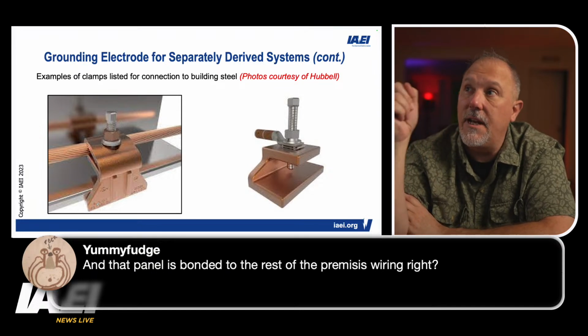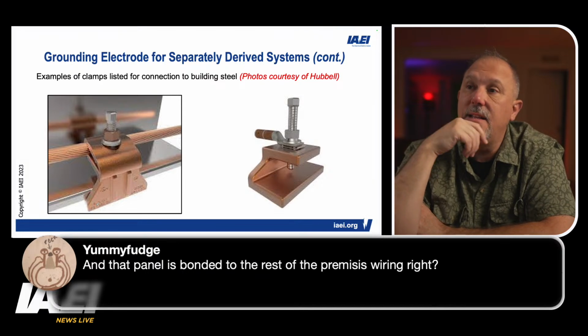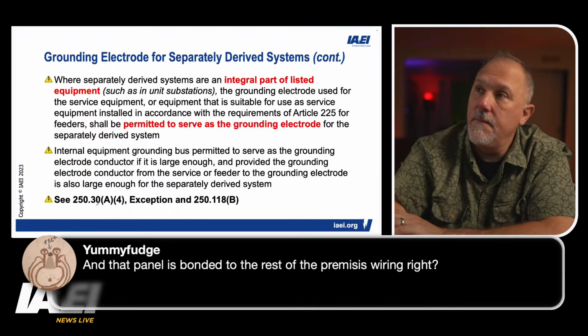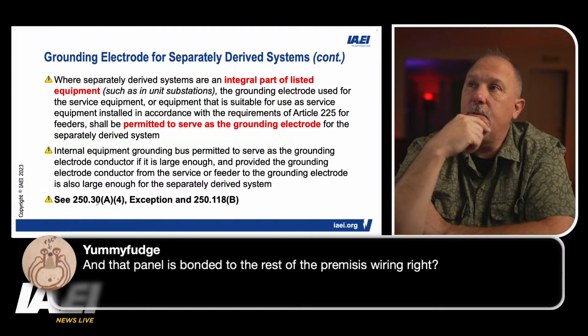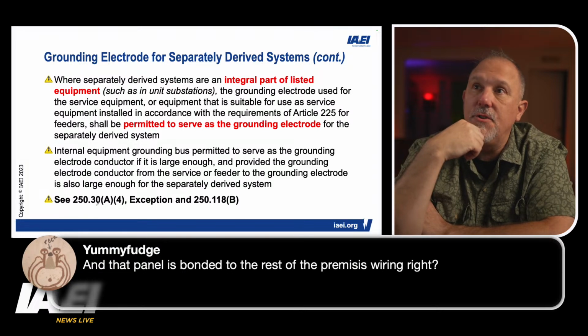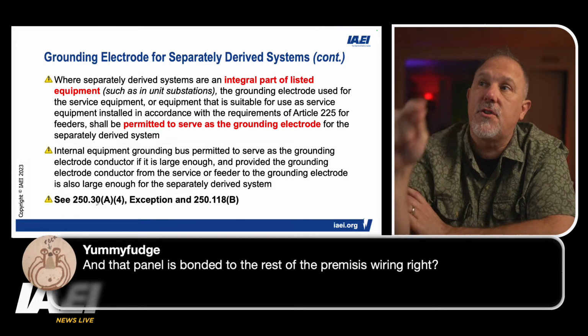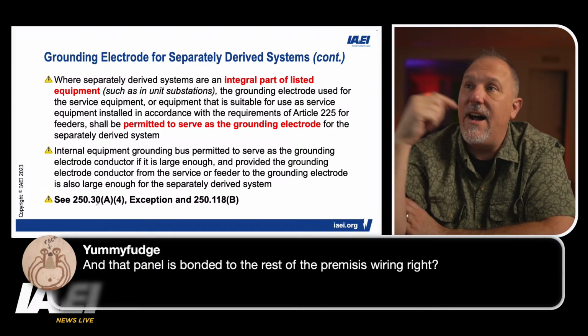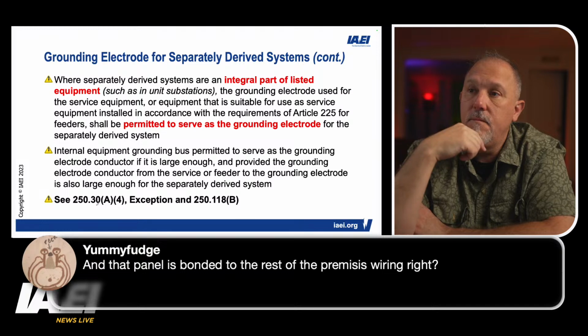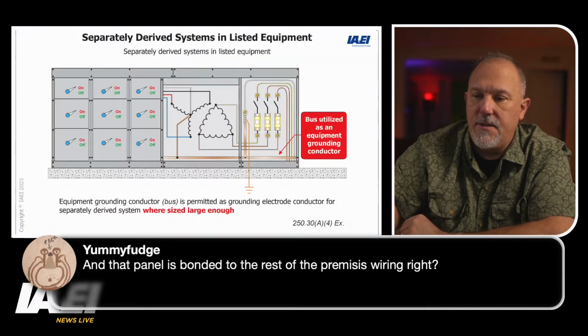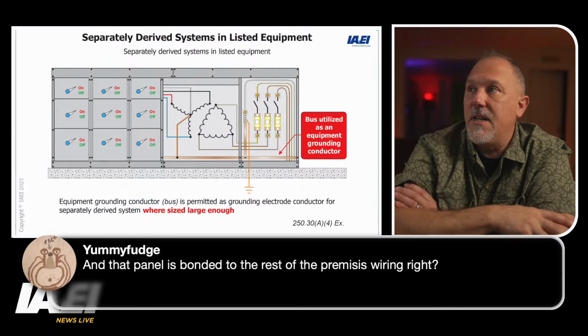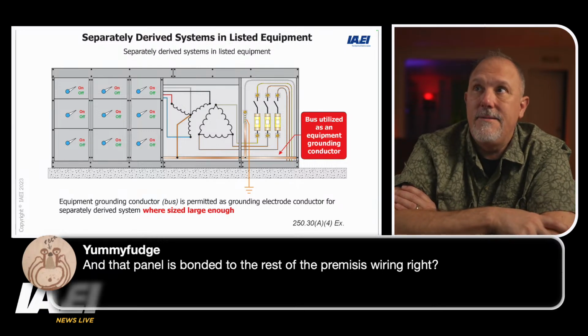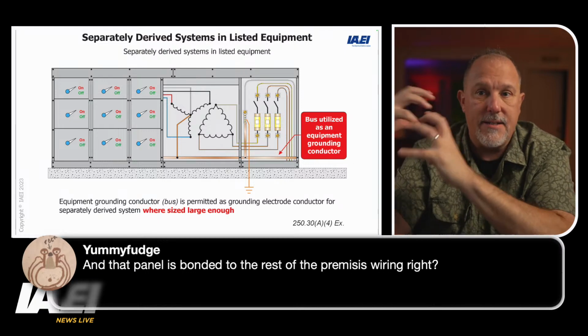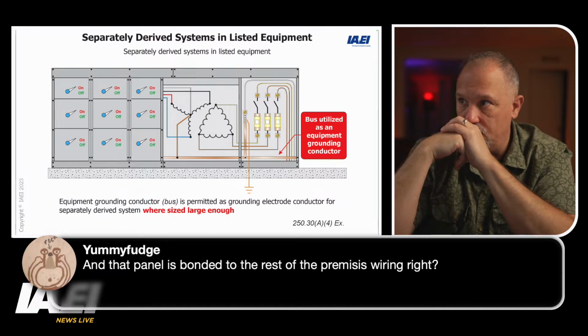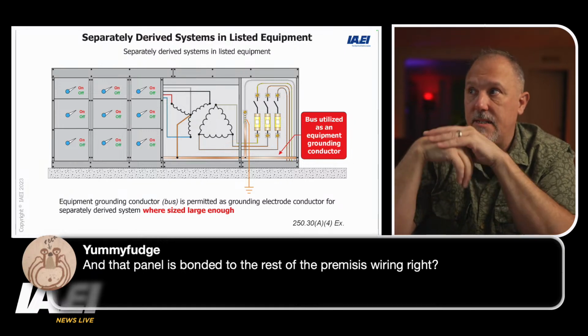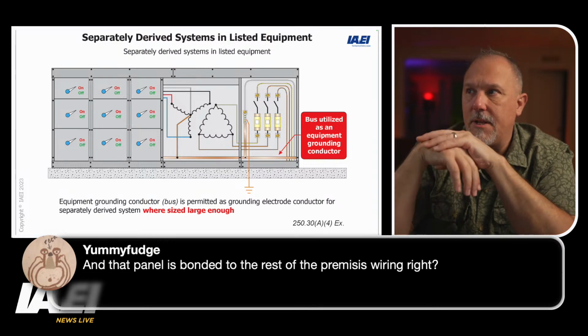Examples of clamps listed for the connection to building steel. That's a sweet little Hubbell product there. Separately derived systems are an integral part of listed equipment. The grounding electrode used for the service equipment, or equipment that is suitable for use as service equipment installed in accordance with the requirements of 225, shall be permitted to serve as the grounding electrode. I think we have an image of that too. There's your bus utilized as an equipment grounding conductor for a separately derived system. That entire assembly is listed for that application, and that bus is listed for the application.